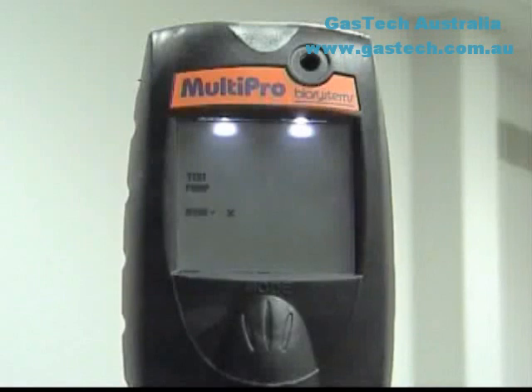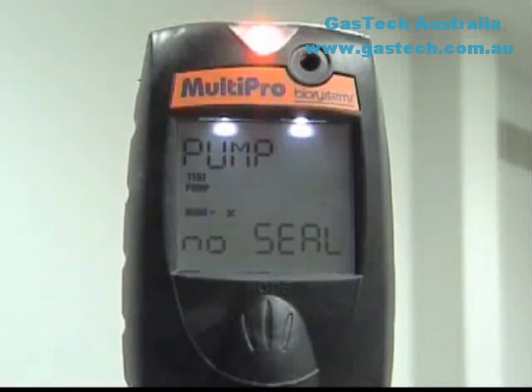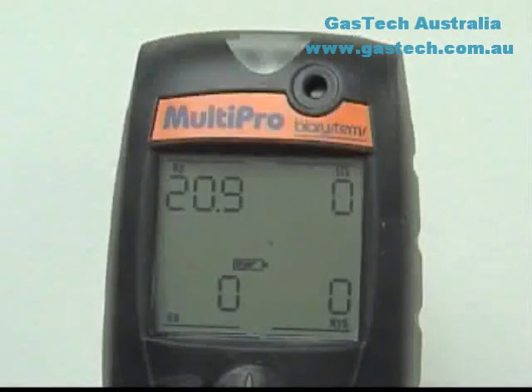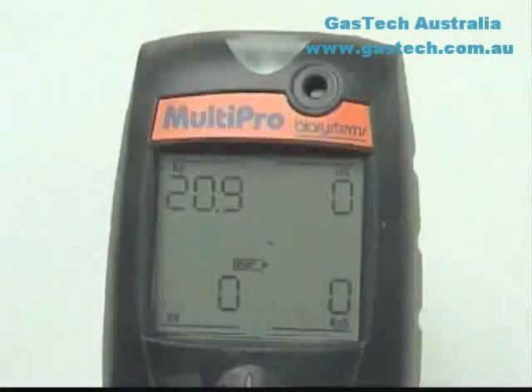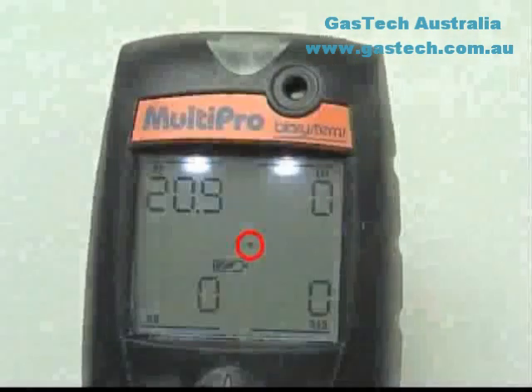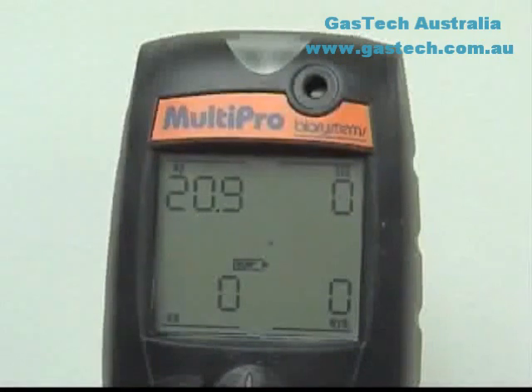If the Multipro is unable to detect a proper seal between the instrument and the pump, the display will instruct you to remove the pump. Once the startup sequence is completed, the current gas reading screen will be shown. Readings are updated in real time. At the center of the display is a heart symbol that will beat every few seconds to let you know that the instrument is functioning.